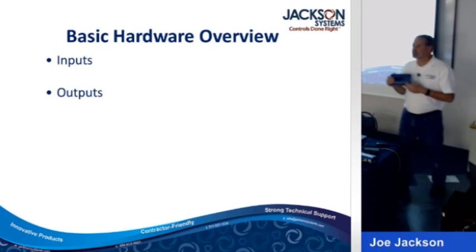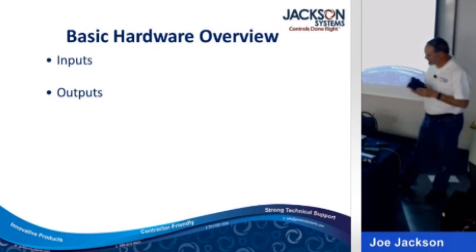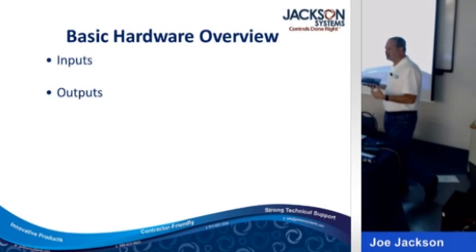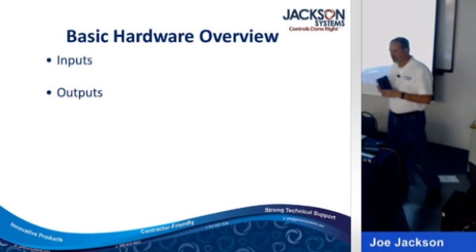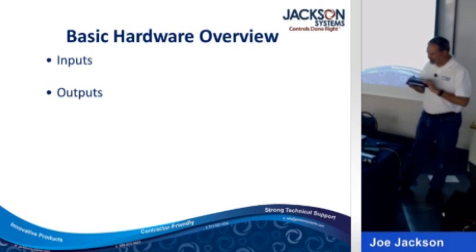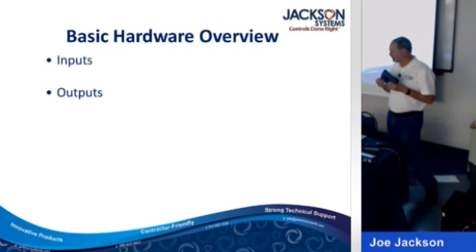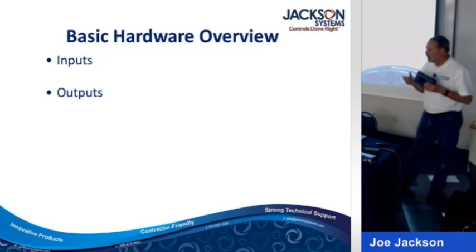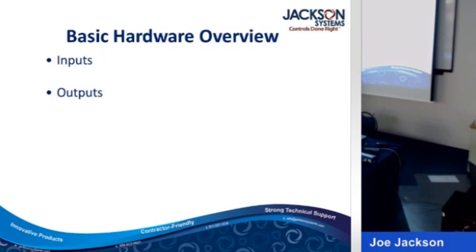And actually, the outputs are the same way today. The way Distech has decided to do it, so that they didn't have to have some digital outputs and some analog outputs, they decided to make all of their outputs on the basic controller universal. What they do is they put out 0 to 10 volts, they'll put out 4 to 20 milliamps, or if you want to turn something on and off, it puts out 12 volts DC, and we pull in a 12 volt DC relay. So I can take any output and set it up to control my damper actuator at 0 to 10. Actually, Belimo uses 2 to 10. Or a Belimo valve, also 2 to 10.